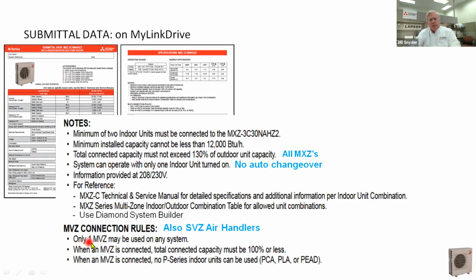Only this particular unit says only one MVZ system can be used, one air handler on this 30. On the 4-ton, I believe we can use 2, but that's all found in these notes. So if you ever have a question on this, the submittal data is the best place to find that information, or give us a call, and we'll walk you through it.